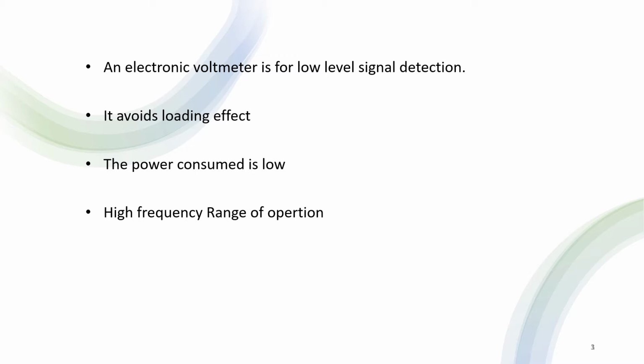Here, if the signal levels are low, then mechanical deflection types of instruments produce a loading effect. That means the instrument will consume an appreciable amount of power and there is a chance that the signal may be lost. But electronic instruments are capable of providing power so that we can measure a voltage in terms of microvolts also.